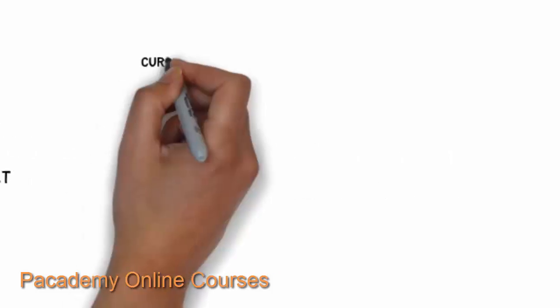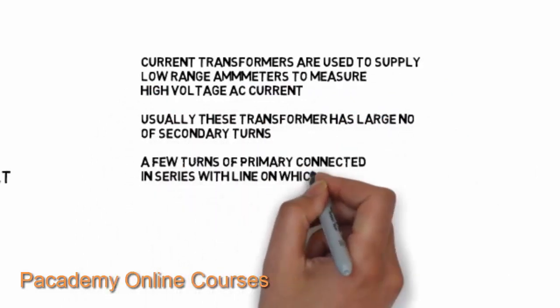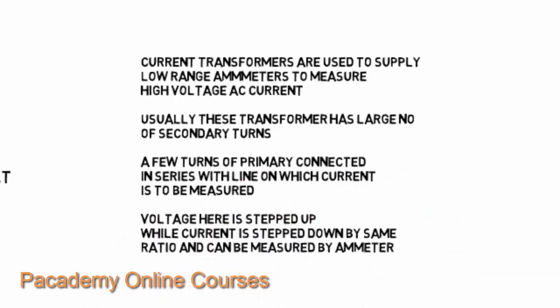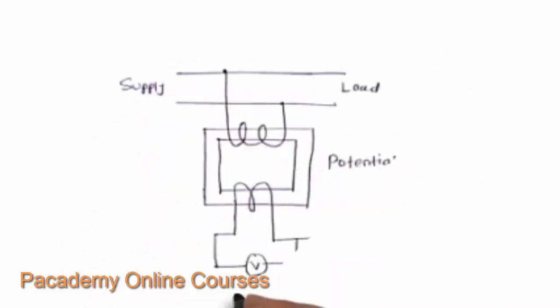The next kind of transformer is a current transformer. These are used to supply a low-range ammeter to measure high voltage AC current. This transformer has a large number of secondary turns while the primary has only a few turns, which is connected in series to the line on which the current is to be measured. The voltage is stepped up on the secondary while the current is stepped down by the same ratio, and it can be easily measured by the ammeter, which is calibrated to measure the current considering the step-down ratio.